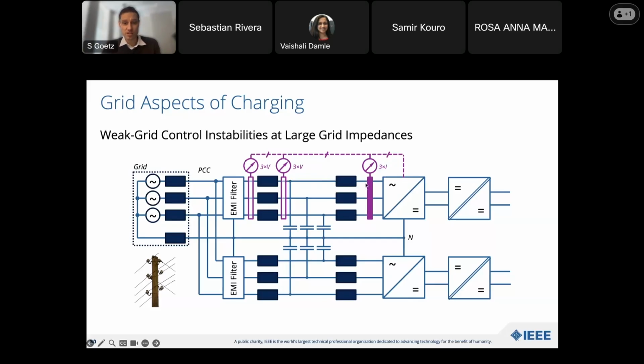Here are two chargers shown. Let's assume that charger is just turned on and draws some current. That means the voltage at the point of common coupling will decrease. The other charger, however, is already charging and wants to keep its power constant. Voltage decreases, so it increases its current, and the voltage decreases further. The other charger is also by then in constant power mode, so it will suck harder and increase its current too. This leads to positive reinforcement and can destabilize your grid locally.